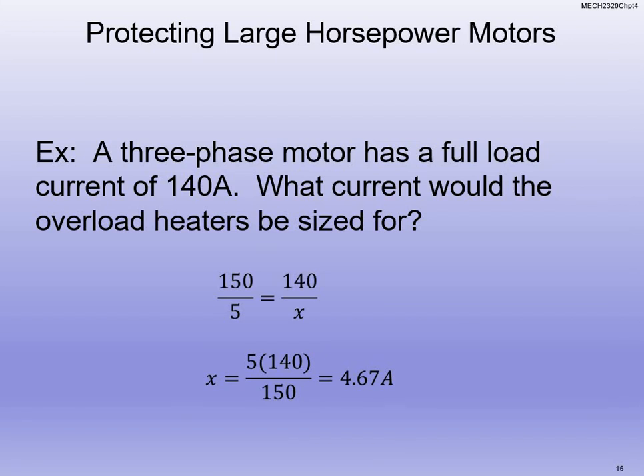You don't want to size right at that specified value, because then it'll trip if it goes up. But for the most part, you usually take 125% of the motor full load current is generally how you size everything, and that's specified in the National Electrical Code book.